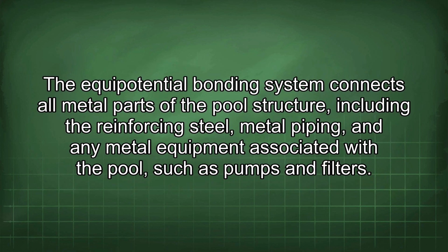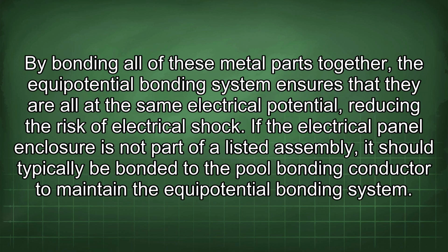The equipotential bonding system connects all metal parts of the pool structure, including the reinforcing steel, metal piping, and any metal equipment associated with the pool, such as pumps and filters. By bonding all of these metal parts together, the equipotential bonding system ensures that they are all at the same electrical potential, reducing the risk of electrical shock.